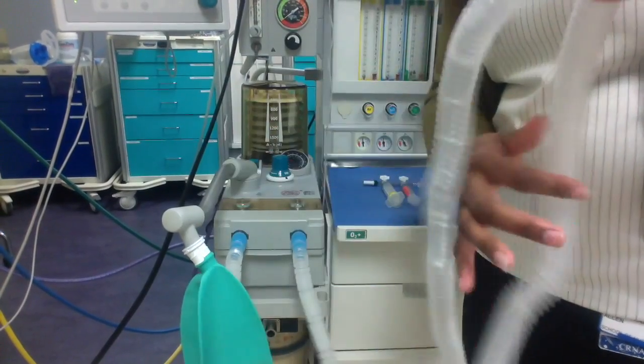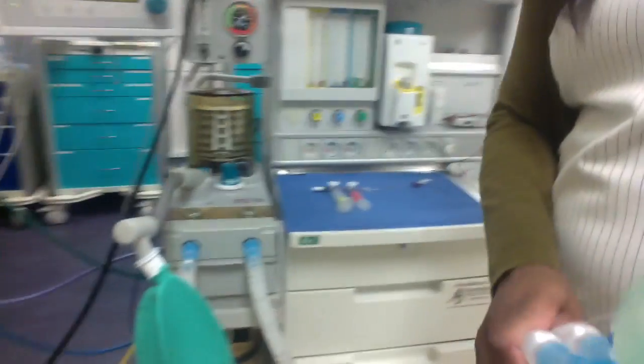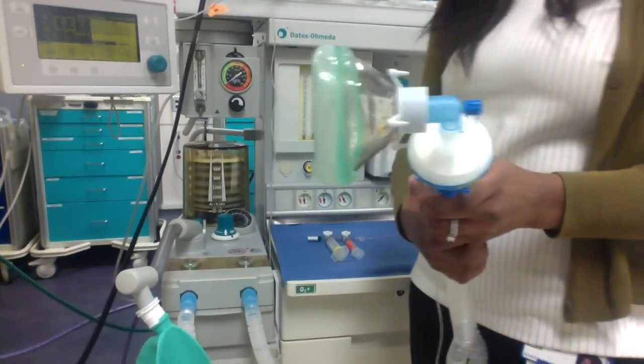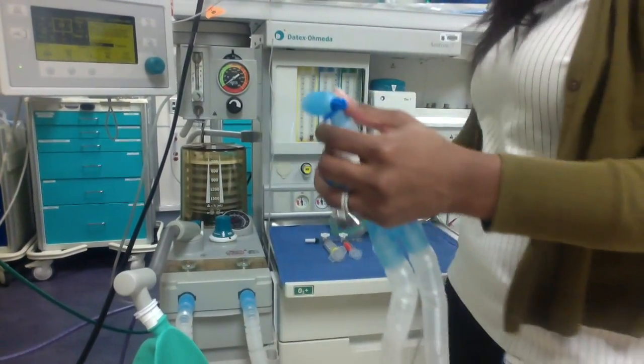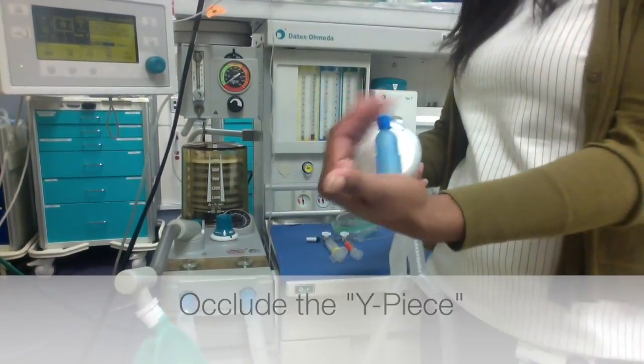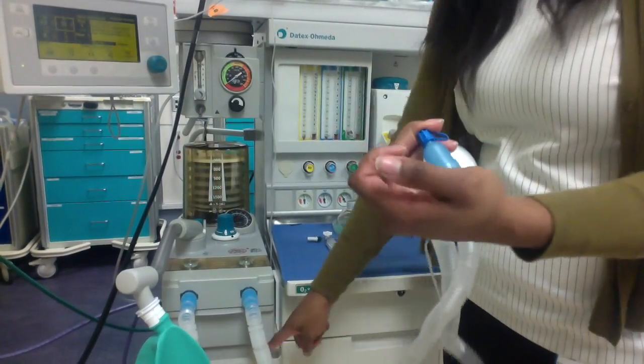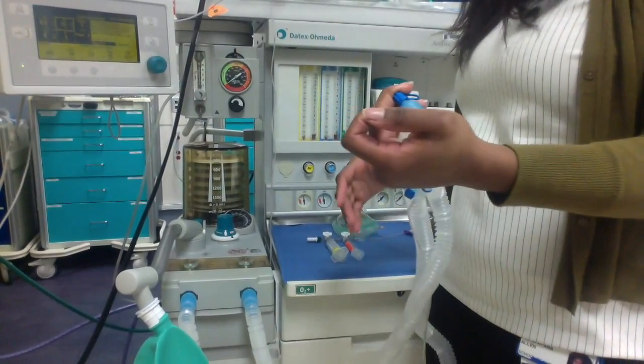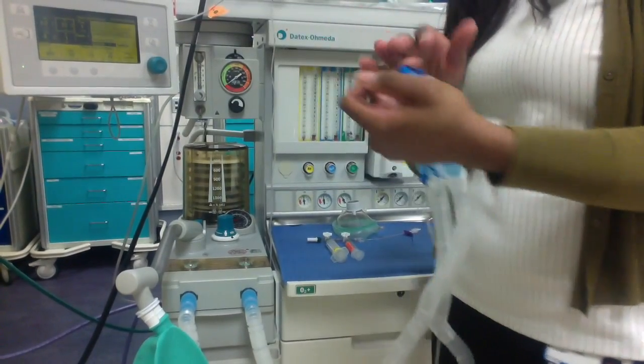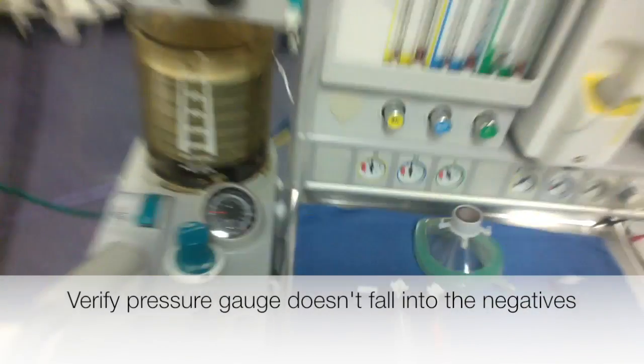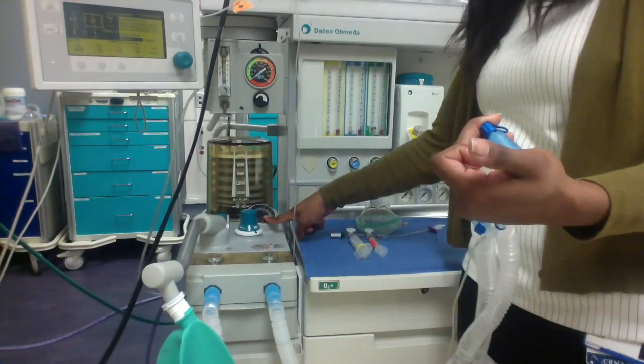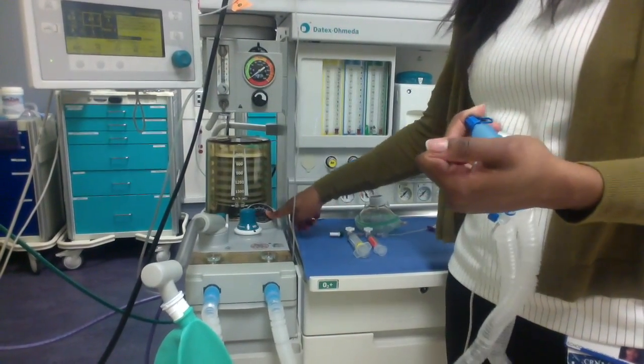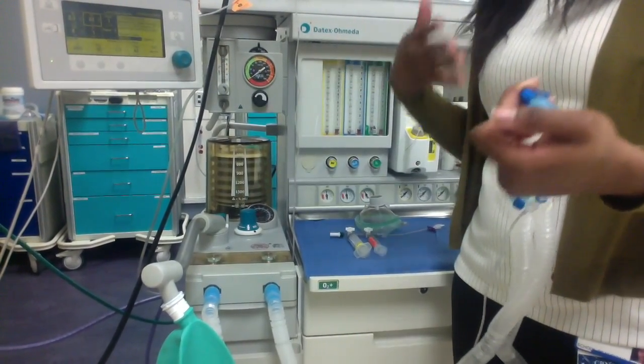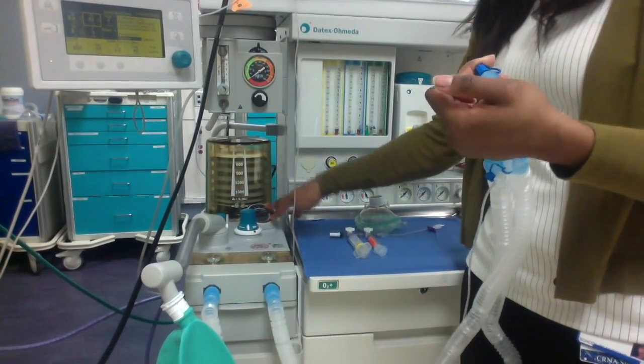There's an inspiratory and an expiratory limb. You'll see things like this in an ICU. So I take the mouthpiece off, and I occlude it with my hand. There's also a knob down here that you can use if you want. So what I do is, once I occlude it, I want to make sure that this pressure gauge here doesn't go below 0. If this were to read below 0 centimeters of water, that would mean that there is suction, and you do not want to suction your patient when you connect them to your vent. It's not reading below 0 centimeters of water, so that's good.